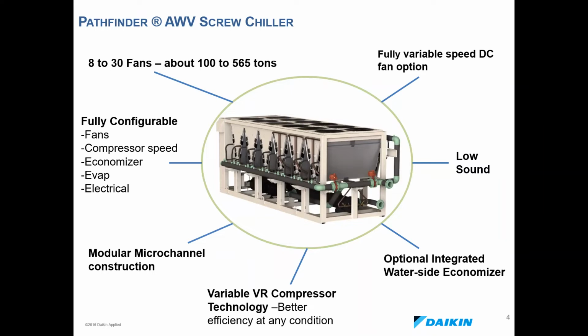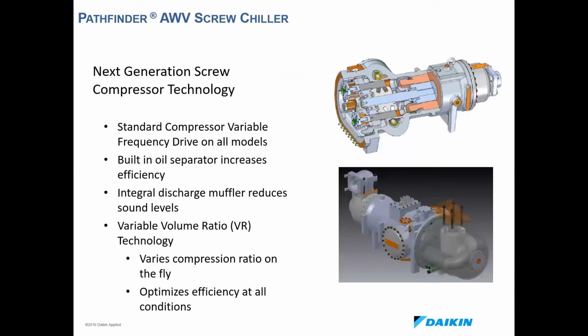You've also got the micro channel construction, which is done in a modular way with these V banks. So these V banks can be pulled out and serviced separately. And then we've also got the low sound options, which are in the form of the internal discharge compressor muffler, which is going to be standard. You also have sound wraps, and then you also have a sound enclosure option, which will all be selectable in Daikin tools. And then the main driver for the efficiency for this product is going to be the VVR technology, which is going to optimize your performance at any operating condition. And we'll go into the VVR now.